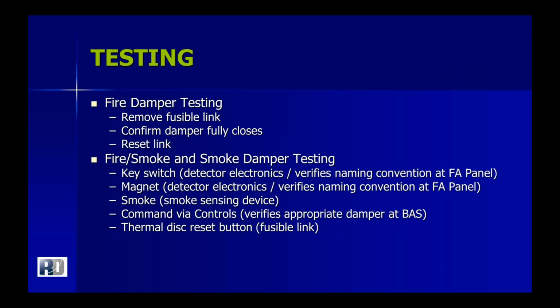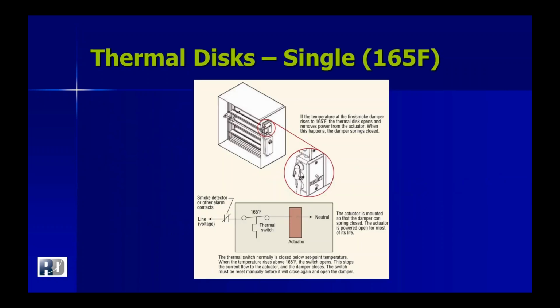There's also the thermal disk reset button. So this here is a picture of a single thermal disk. This is basically part of a fire smoke damper. It's the fire aspect of a fire smoke damper. So you have this little reset button and disk that's on the side of your duct. When these are in place, you need to be able to have access to push these on the inside to release the disk. So you're pushing the button. It basically pops the fusible link, per se, so that it removes the power and allows that fire smoke damper to close.